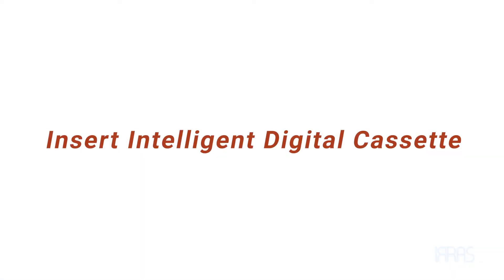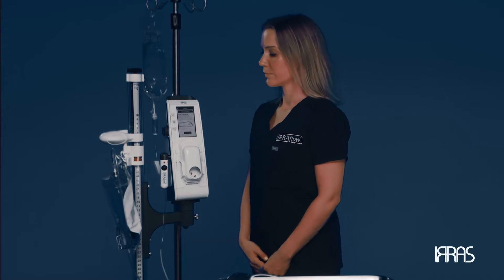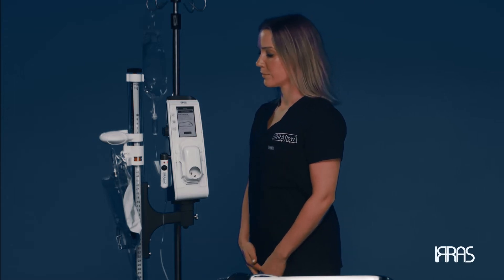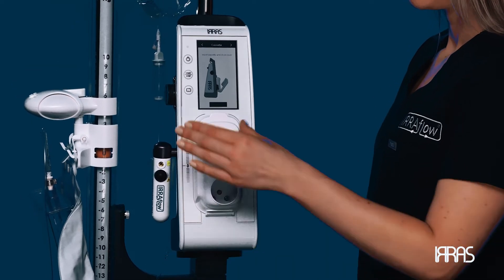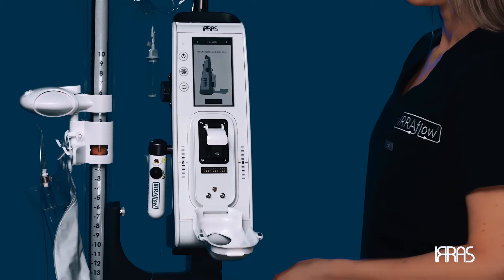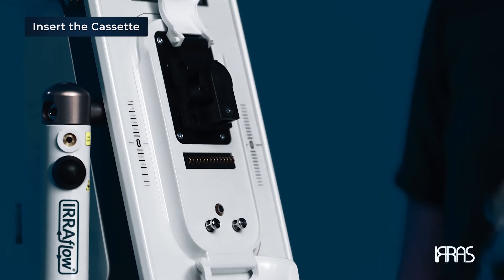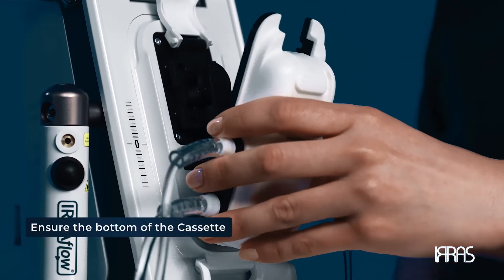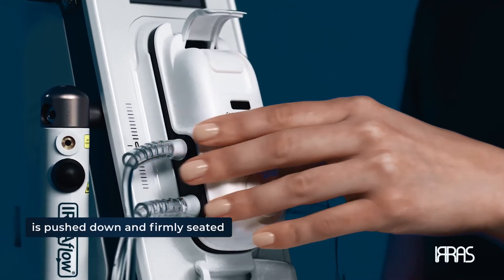Insert the intelligent digital cassette. Now that we have this completed, we are ready to attach the intelligent digital cassette onto the IRRAflow control unit. To start, open the cassette door. The control unit will prompt you to attach the cassette, close the cassette lever, and then close the cassette door. First insert the cassette by inserting the bottom and then the top. Ensure the cassette is pushed down and firmly seated.